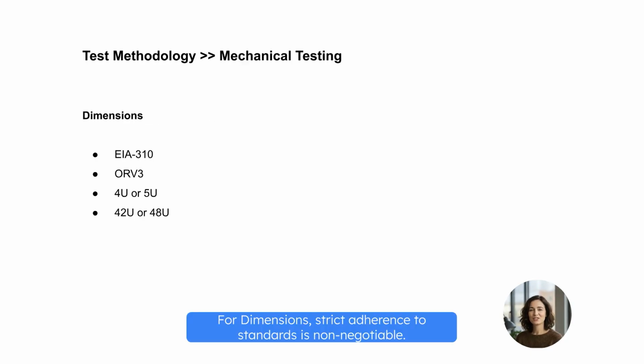For dimensions, strict adherence to standards is non-negotiable. Rack mount units must fit EIA 310 or ORV3 frames. You are designing typically for 4U or 5U increments to ensure ease of deployment. In contrast, in-row CDUs operate at the rack scale. These units conform to full cabinet heights, typically 42U or 48U, aligning physically with the IT rows to deliver maximum cooling capacity.